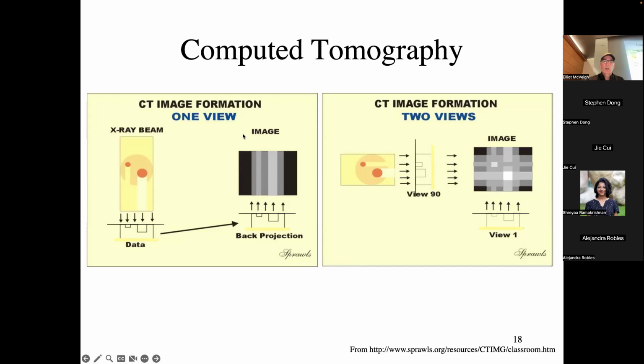Okay. So what we do is we estimate the number of X-rays that were lost or absorbed in this pathway and the number that were absorbed in this pathway, and I plot that function along here and project it back down through that space. This is the primary projection image I get of this two-circle object. I get a background and I get two different stripes that are the width of those objects, right?